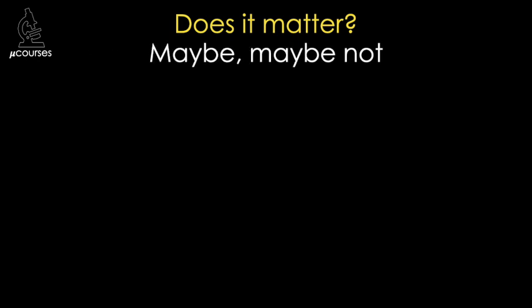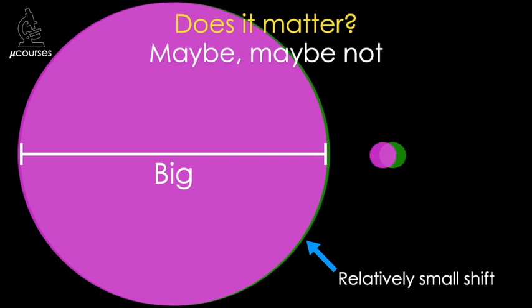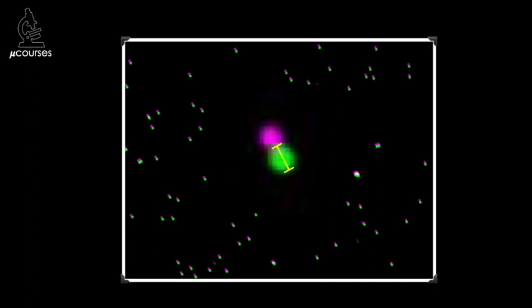Might a chromatic shift be affecting your data? Maybe or maybe not. When imaging objects that are big, relatively small chromatic shifts may not cause a significant change in your measurements. And if imaging with a lower numerical aperture lens, you may not even be able to resolve the shift — in which case it might not be worth the time and effort to correct for it. In general, as the size of the objects decrease and resolution increases, chromatic shifts tend to become more of a problem. The multicolor fluorescent beads we looked at earlier are just below the resolution limit of this microscope, and if we zoom in on one of the beads, you can see that the size of the bead is roughly the same as the size of the shift. This is an example of when chromatic shift might lead you to the wrong conclusion.